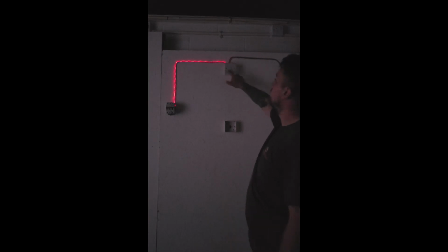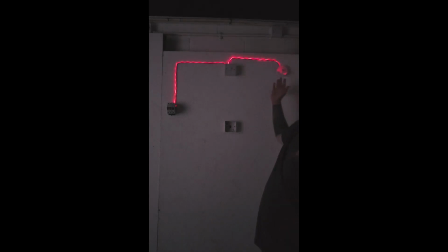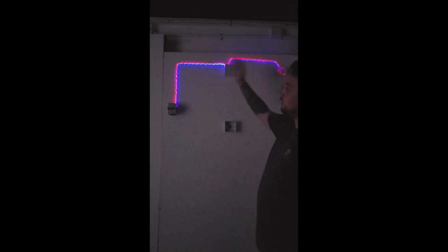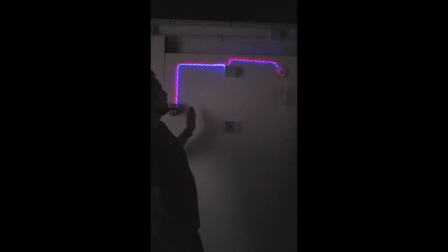So when your breaker goes on, your current flows through your brown wire up to the common of the switch. So when you turn your switch on, it bridges from common to L1, which would then send your current up to the pendant. And when and only when your lamp's in, it completes the circuit, sending your voltage back on your neutral, or at least getting your potential difference across line and neutral here to send your voltage back.